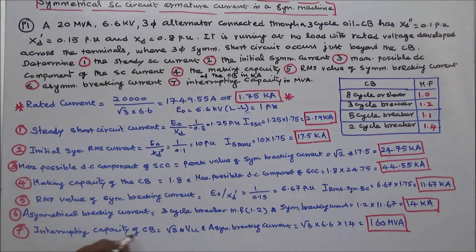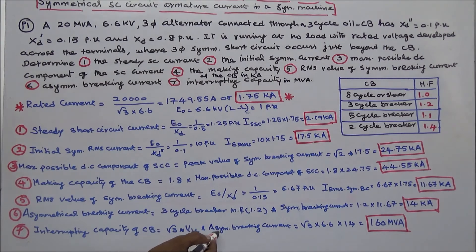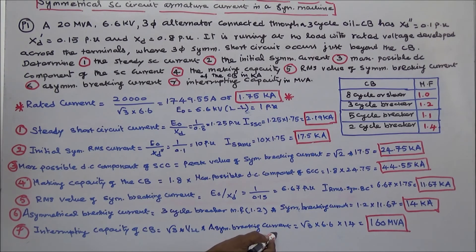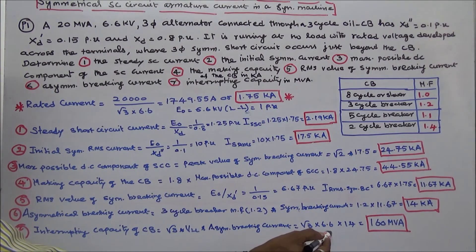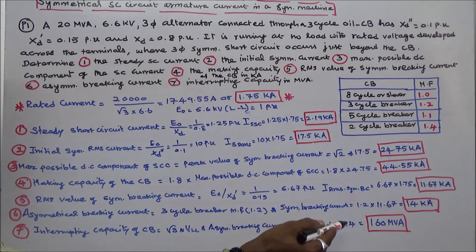Last is the interrupting capacity of the circuit breaker. That equals root 3 into line-to-line voltage into asymmetrical breaking current. Asymmetrical breaking current is 14 kA, root 3 into 6.6 KV into 14 gives the interrupting capacity of the circuit breaker as 160 MVA. This way we work out this problem. Thanks for listening.